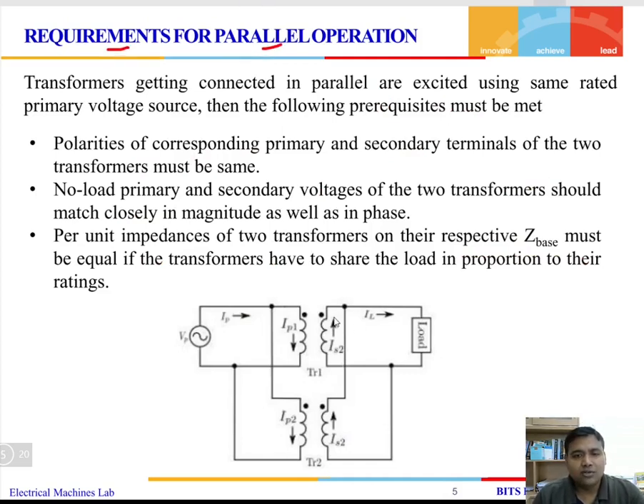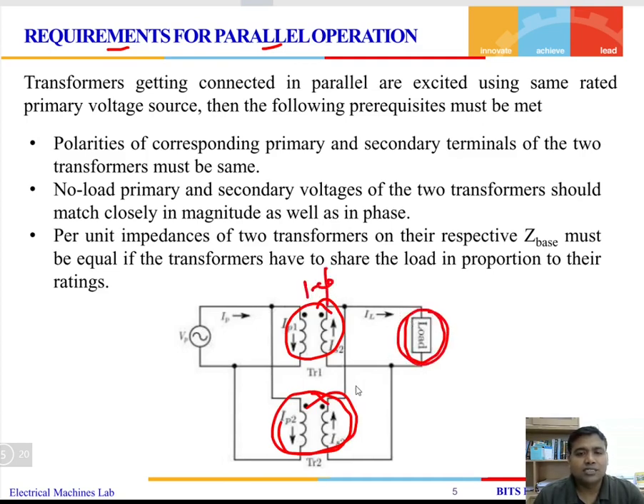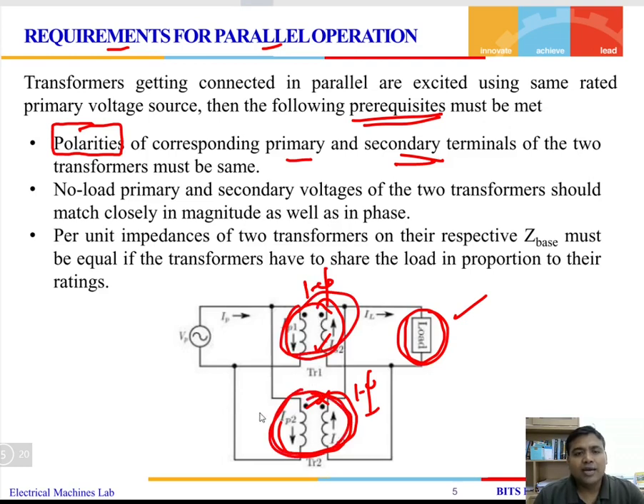Here we can see transformer 1 and transformer 2, which are connected to meet a load. Both are single-phase transformers. So two transformers will be connected in parallel to meet a load. Then there are certain conditions or prerequisites that must be fulfilled. The first requisite is related to polarity. The polarity of the primary and secondary terminals of the two transformers should be the same. We can see transformers 1 and 2, whose polarity must be the same with respect to the primary side and the secondary side. This side is the primary, which is connected to the source, and this side is the secondary, which is connected to the load. Both polarities must be the same.